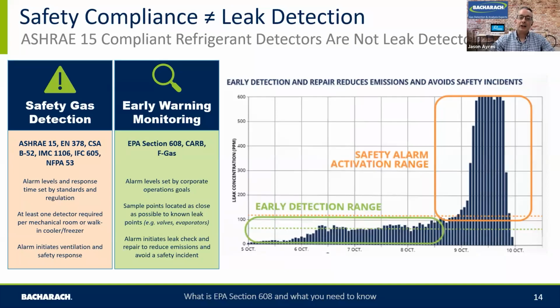This is really about protecting the personnel in a space. It's gross leak detection. It will tell you you've got a refrigerant emission at a very high level, and it will allow you to evacuate the area and protect people. Unfortunately, once you're detecting refrigerant at that high level, we're talking the 800 to 1000 ppm, these are the exposure limits and the safety regulations. You've got a large refrigerant loss. You're at the wrong end of the curve. Yes, you're protecting the people, but are you getting to a point of reducing the refrigerant loss? Where can you go from there?